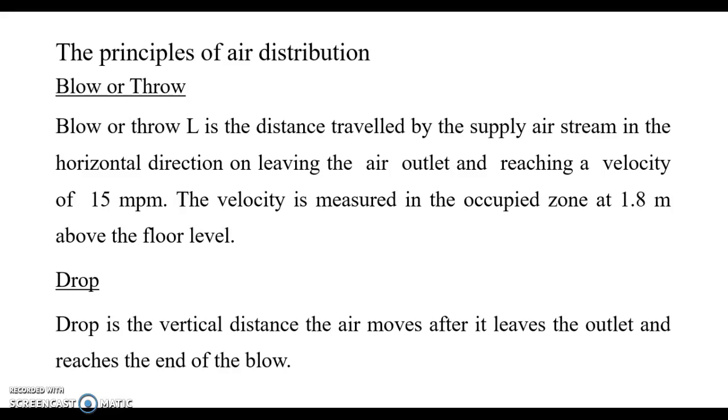Drop is the vertical distance the air moves after it leaves the outlet and reaches the end of the blow. Blow means horizontal distance, drop means vertical distance traveled by the air.